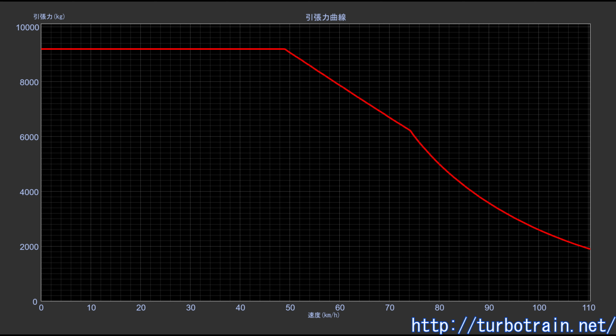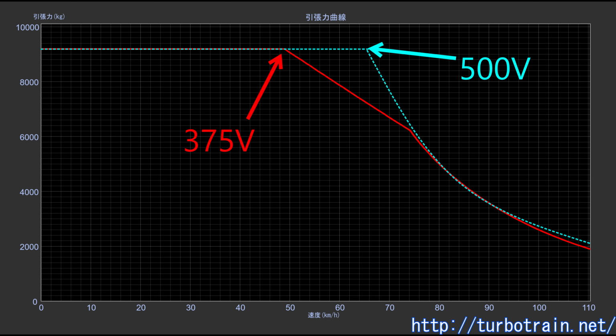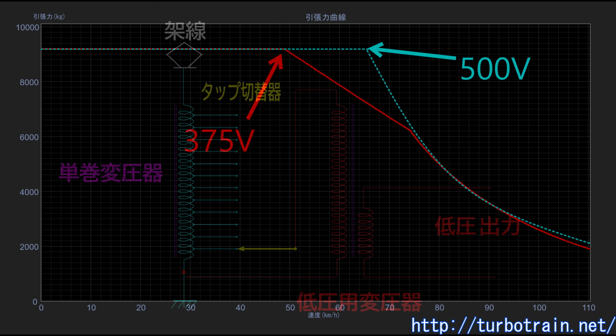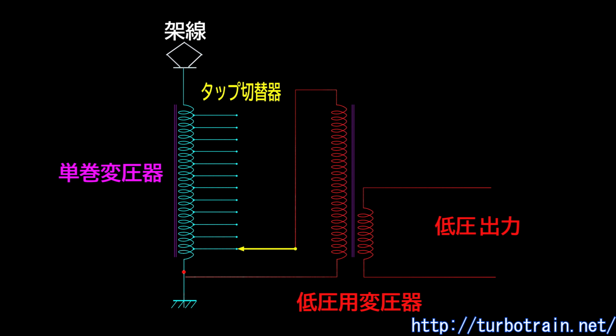Thus, the bold approach was to drive the existing MT54 motors at high voltage to maintain torque at high speeds. These motors had a history of being used in electric braking mode, where the generated voltage exceeded the rated voltage, without insulation issues. This is where the advantage of AC systems, which can freely adjust voltage through transformers, came into play.